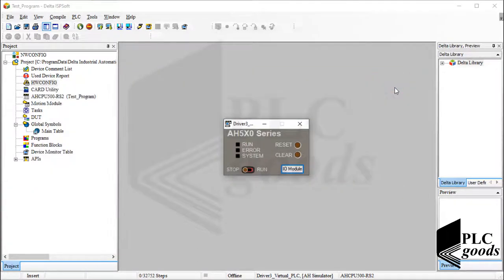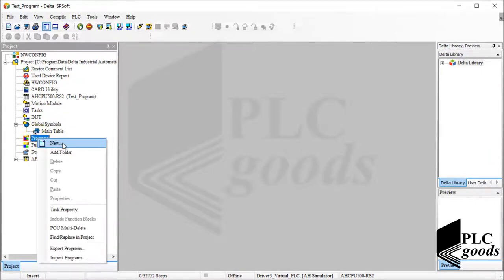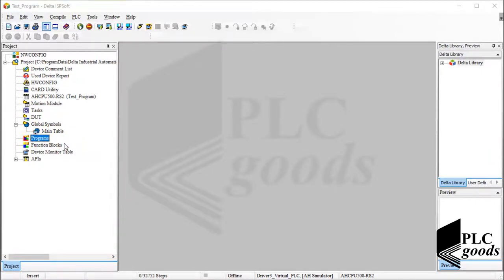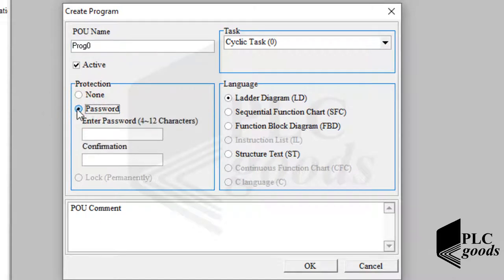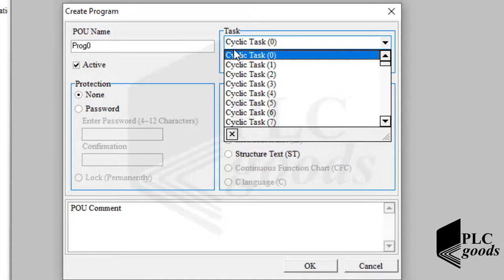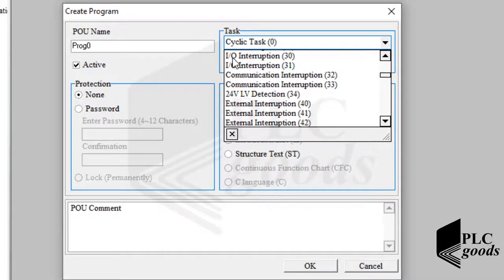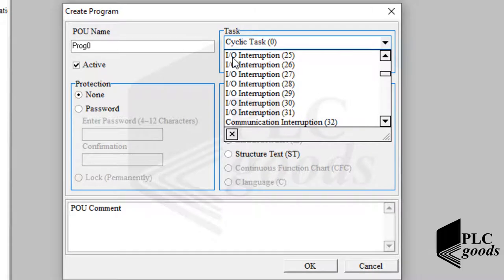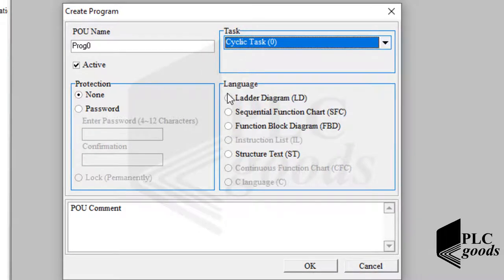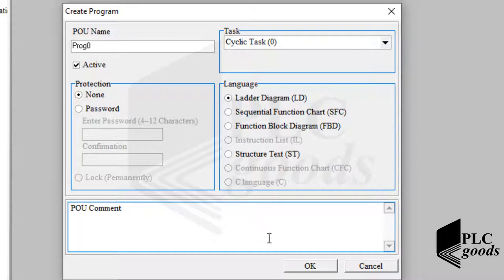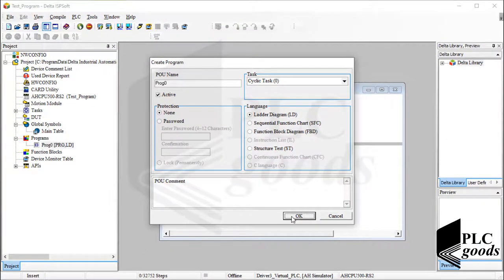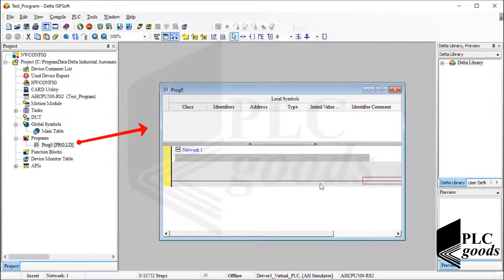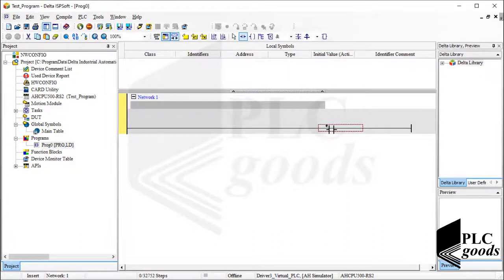After hardware configuration, let's write a simple program and see how it can be tested. So on the left side, let me right click on the programs icon and select new to write a new program. Here I can determine a name, active or inactive the new program, and determine a password to protect it. On the right side I can determine how it must be executed. Let's select cyclic task. So PLC will execute the program continuously. After that I can determine the programming language. The selected controller supports 4 languages. Let's select ladder diagram. Finally I can write a comment for the new program. Let me click on OK. Now let me write a simple program to turn on 3 digital outputs.